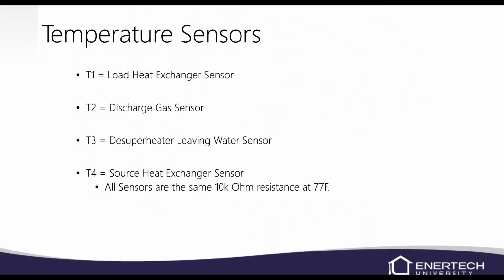Again, T1 is your load heat exchanger sensor. T2 is a discharge gas sensor. T3 is a desuperheater leaving water sensor. And T4 is your source heat exchanger. Now, all sensors are the same. The only thing really different on them is the length of the wire. But they're all 10K at 77 degrees.